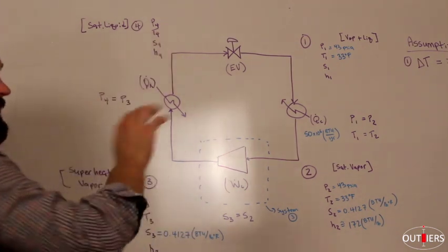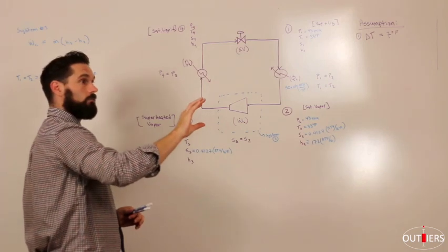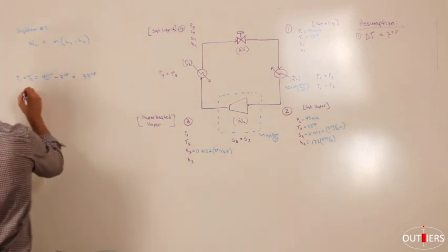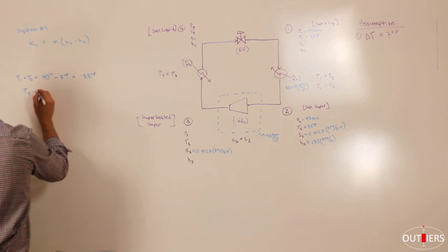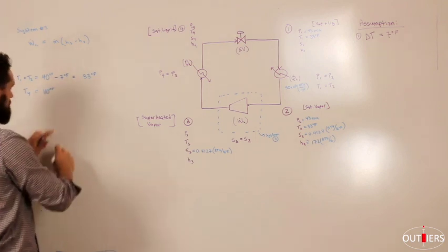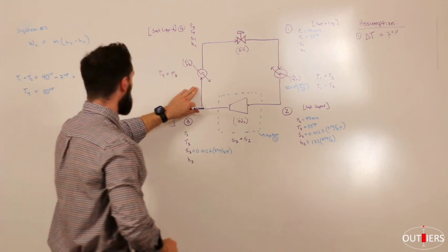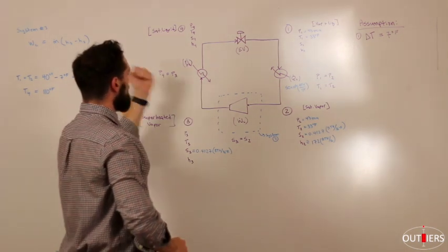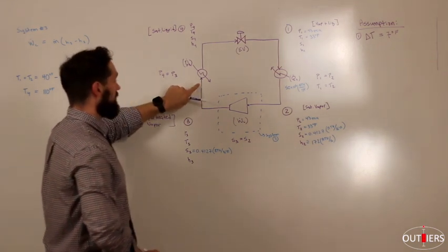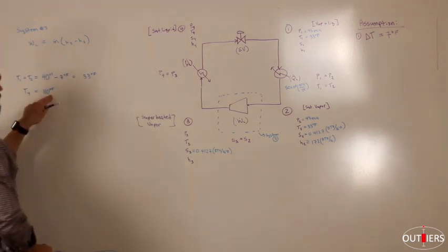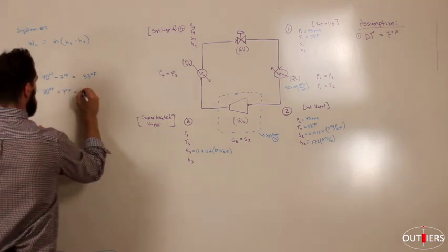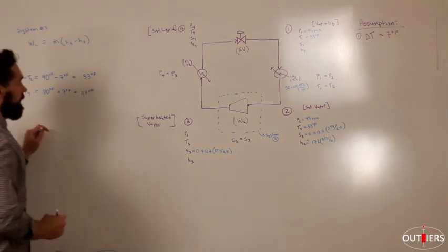So we want to say T4 needs to be at 117 degrees, well, or hotter, but we're using a 7-degree temperature difference. I'll show you how I get there. T4 needs to equal the ambient air, which we assumed is 110 degrees Fahrenheit on a bad day. And remember, because here the fluid is dispelling heat to the environment, the refrigeration fluid here needs to be hotter. It needs to be the hotter substance. So if the outside air is 110 and we want a 7-degree difference, we need to add 7 degrees, and that's how we got our 117 that I just rattled off earlier but didn't show you how.